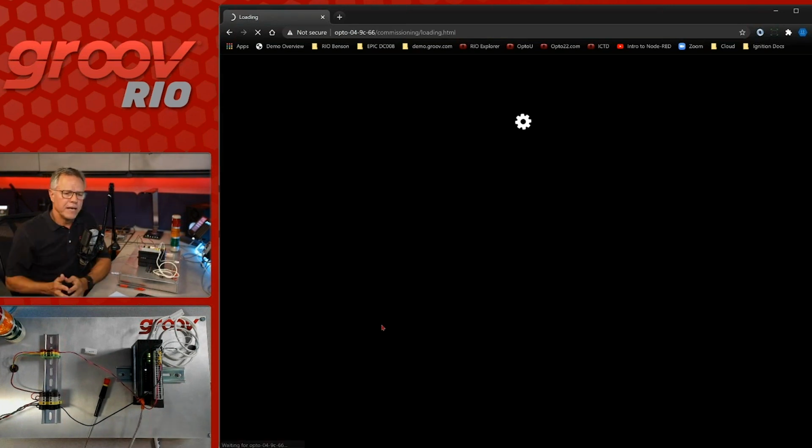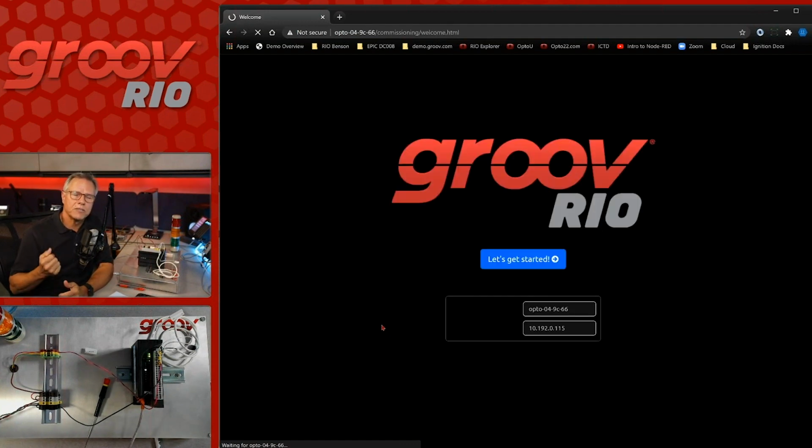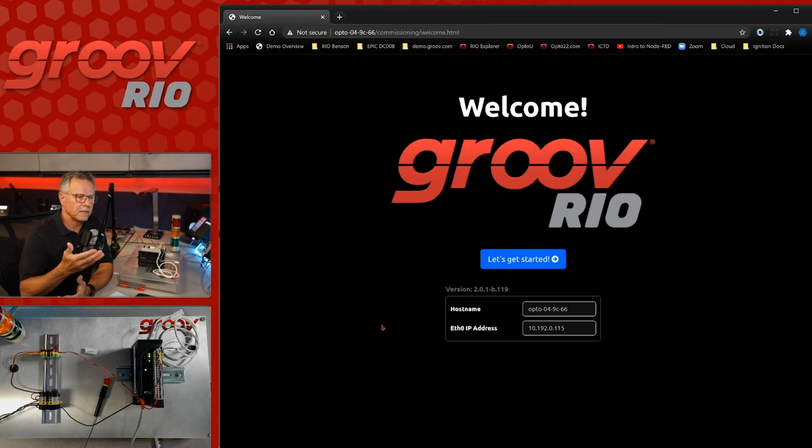There we go. Now, when you first fire up Rio, it's going to recognize it hasn't been commissioned yet, so it automatically goes to the commissioning page. And the reason for that is because, one, we want to know what IP address it got, for example, but it also means that I have to set up an account. You see, Rios don't have, and nor do groov EPICs, a default username and password. No device on the plant floor should. So when you first boot it up, you have to create that account.